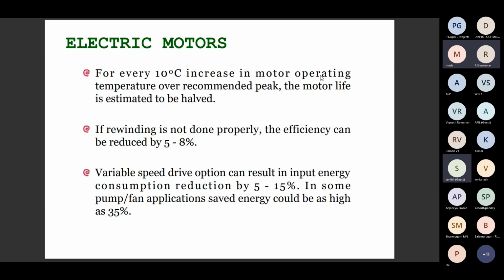So it is very, very important. We are losing more energy in the rewinding area, so a motor should be rewound only 2 or 3 times. Most of the foundries follow TPM and other preventive maintenance schedules. In the history card, the date and area should be noted once the motor is rewound, so that the motor is not rewound more than 3 times. So the maintenance team should be very alert about rewinding the motor.